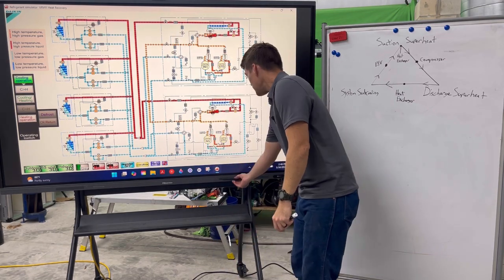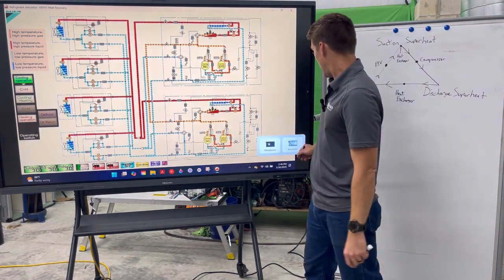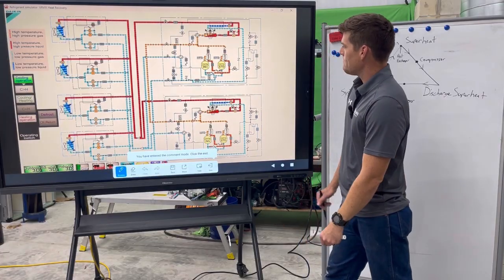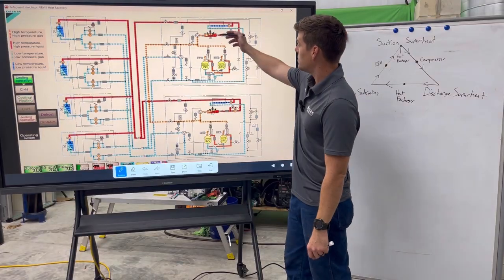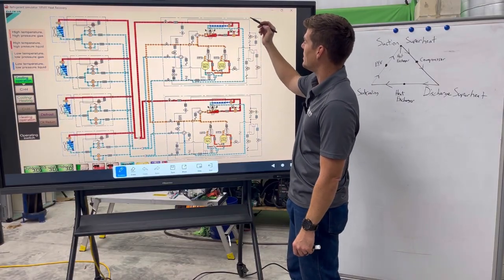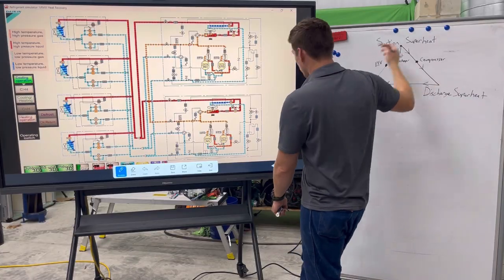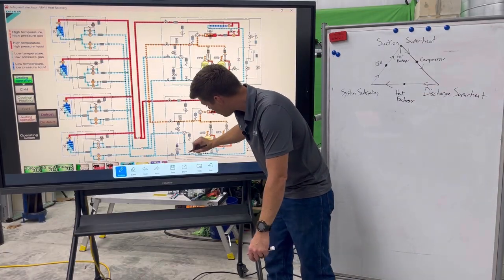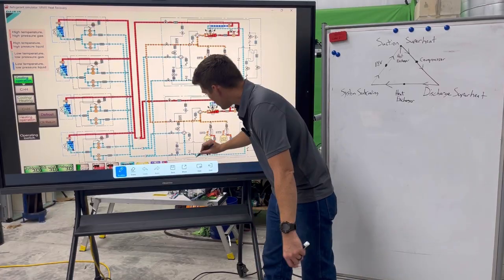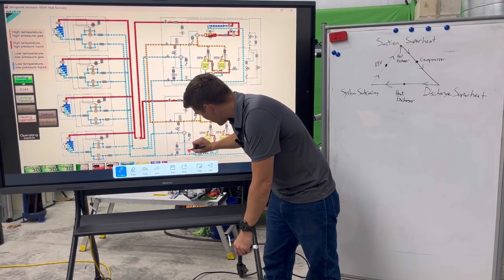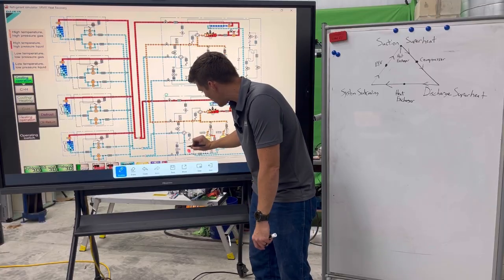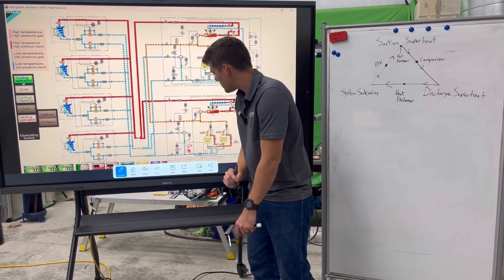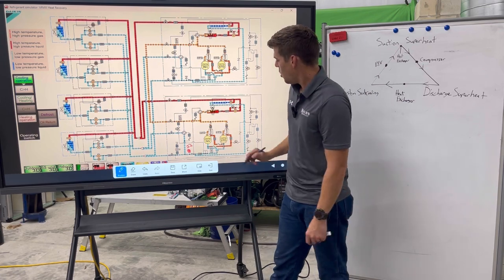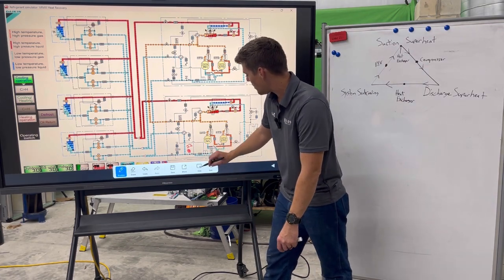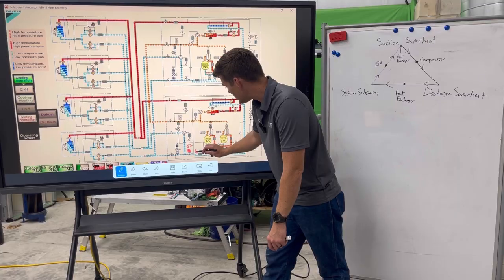Let's get into it. So if I look at this here, right, and let's start annotating. Now we have a system, and it's in cooling mode. What we know about cooling mode is that my outdoor units are taking hot gas and turning it to a liquid. So let's start where we always start, with our suction superheat at the top here. So my suction superheat is what? It's two things. It is my saturated temperature right here on my saturated temperature sensor. Let's say my saturated temperature is 32 degrees, right? That's pretty low. What is my actual suction line temperature coming back to my compressor? Well, let's say that it is 62 degrees.